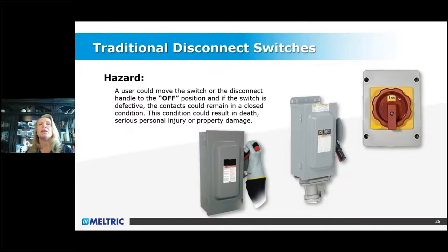The other thing, this standard has specifically said that once you have disconnected the device, you need to open it and verify that all the phases have actually opened. The reason they have that in this standard is because there is an inherent hazard where you can hear that the disconnecting device has opened, but maybe one of the phases was stuck. There have been recalls in 2017 on a popular brand of bladed disconnects, and I got this hazard warning off of that recall. There have also been recalls of a popular brand of rotary disconnects.